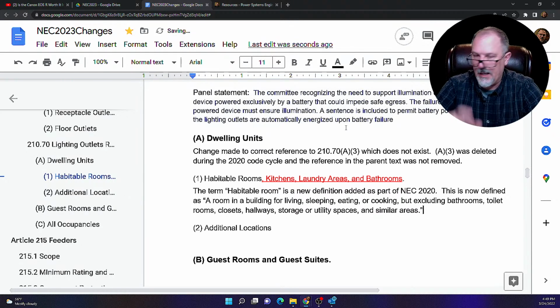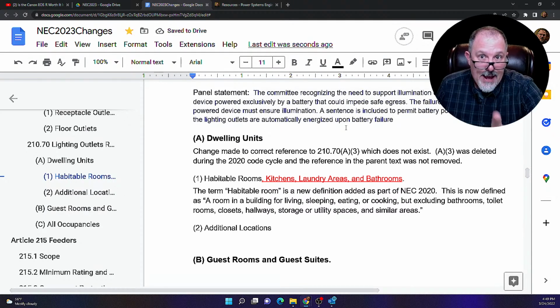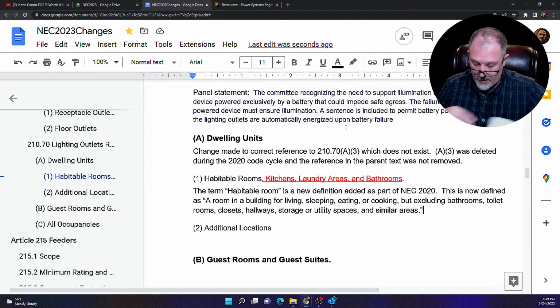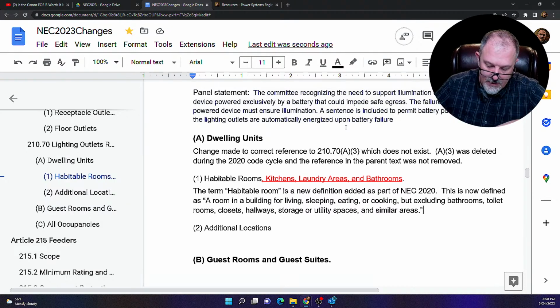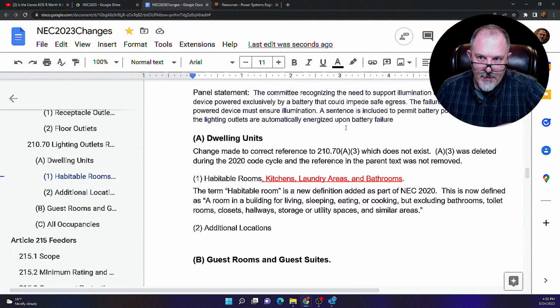Now, knowing that's the definition, let's look at what 210.70A1 says: at least one lighting outlet controlled by a listed wall-mounted control device shall be installed in every habitable room, kitchen, and bathroom. So the problem is the title of the section was just 'habitable rooms,' and it threw in kitchens and bathrooms.